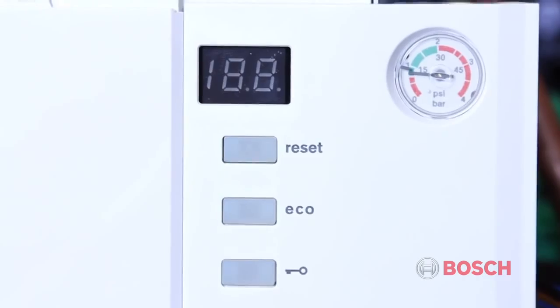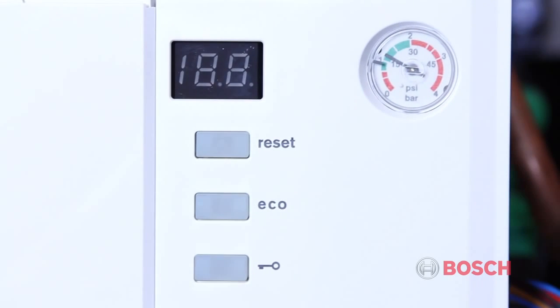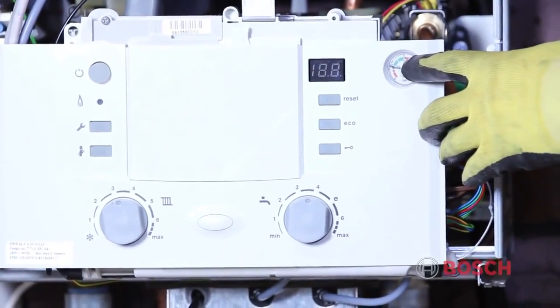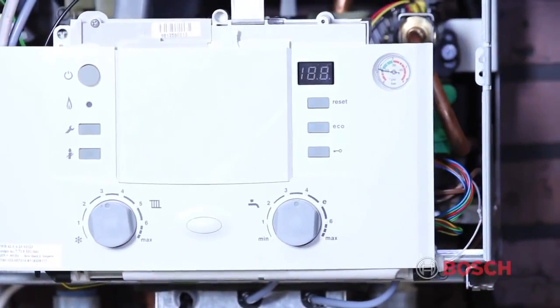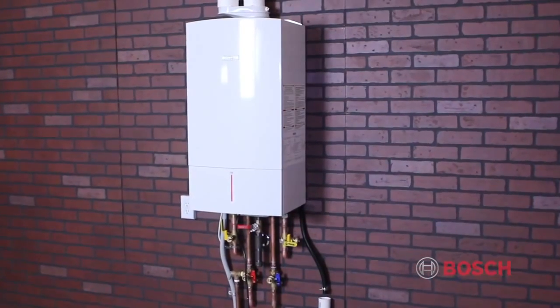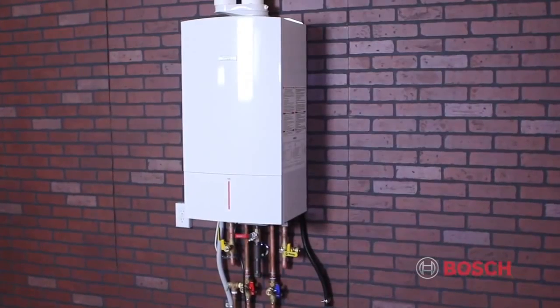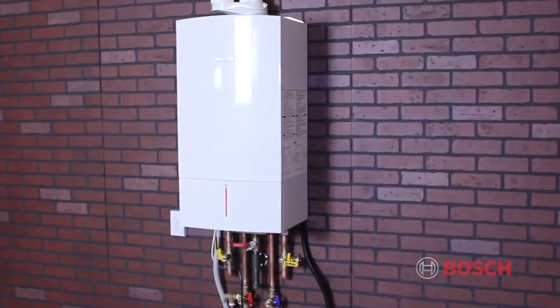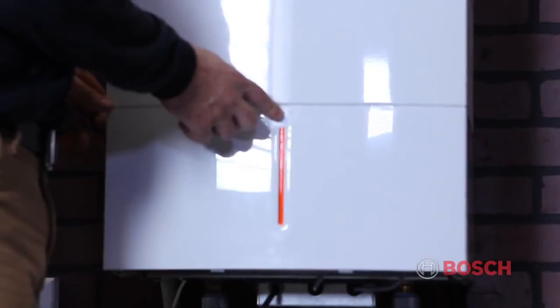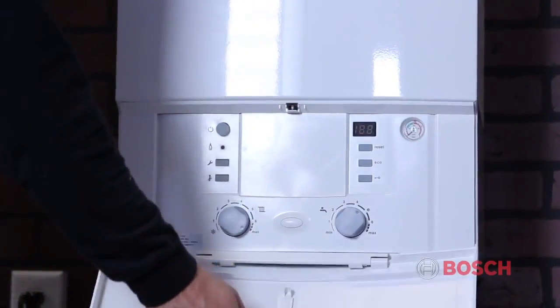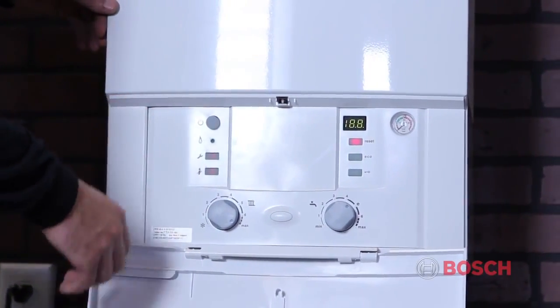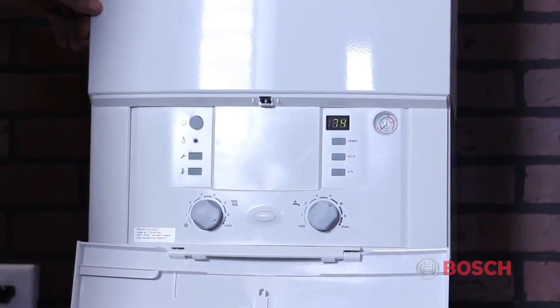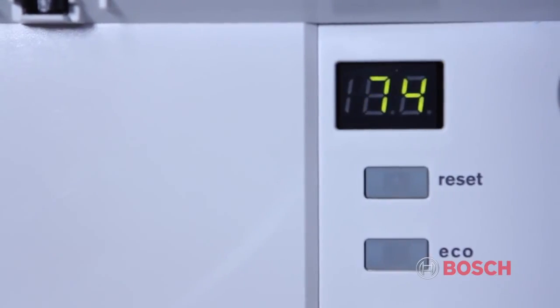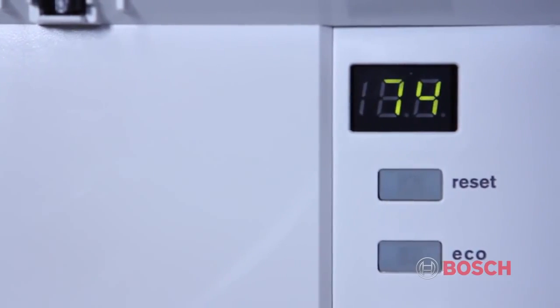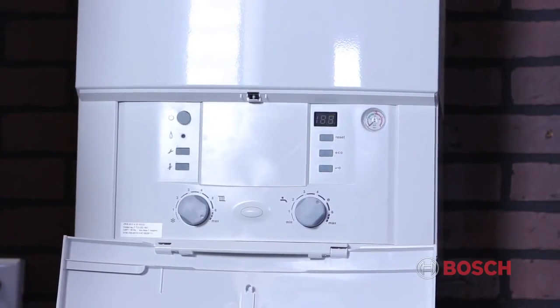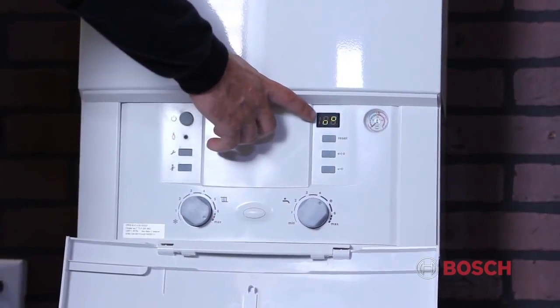Once finished, pressurize the system from 14 to 21 psi, as indicated by the green area on the boiler pressure gauge. Next, turn power onto the boiler. Make sure that the system has been filled with water and the service switch and circuit breakers are in the on position. Press and release the round button in the upper left-hand corner of the Heatronic control. When you first initialize power to the Heatronic, the unit display will flash, alternating between what looks like a percentage sign and the temperature from the primary sensor. This will last about 8 minutes.